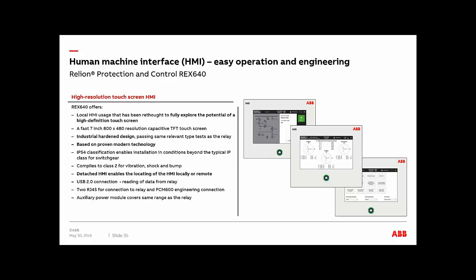Like I said, it's a 7-inch, 800 by 480 resolution TFT touch screen. It's got an industrial hardened design with the IP54 classification, and it complies with class 2 for vibration, shock, and bump. Mounting options are available when you order the relay, so they can be mounted in a wide range of arrangements, since the HMI is detached from the relay. There's a USB available as well on the front of the relay, where you can read data from the relay. There are also 2 RJ45 connections for PCM600, which is a program used for the relay itself. And you have an auxiliary power module that covers the same range as the relay, since the HMI requires its own power supply because it is detached from the main box.